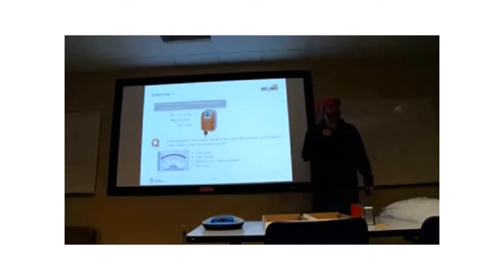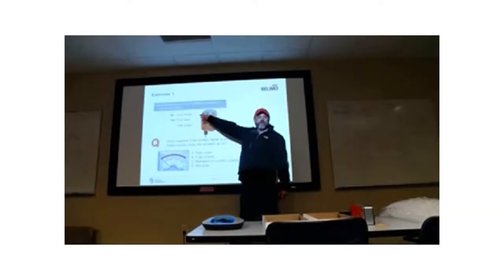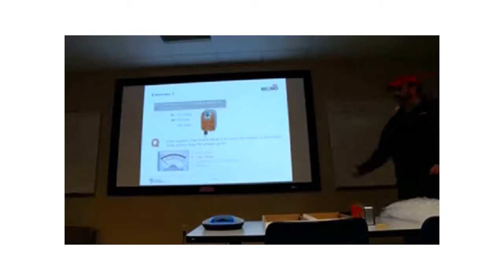You guys got it right. If you ask the question another way: what happens if you remove the control signal from the actuator? You'd see 0 volts on the command, right? So where is it going to go? Wherever that 2 volt position is, because remember, 2 volts could be fully open—it doesn't have to be closed. It could be 2 volts open and 10 volts closed. In this case, 2 volts is the fully closed position. So when you remove that control signal, the actuator sees 0 volts on the command, and the answer is B—0 volts on the third wire, not on the power. You still have power, right? The actuator still has 24 volts, it just doesn't have a command signal. So the answer is B. Does everybody get that? Because that's really important.